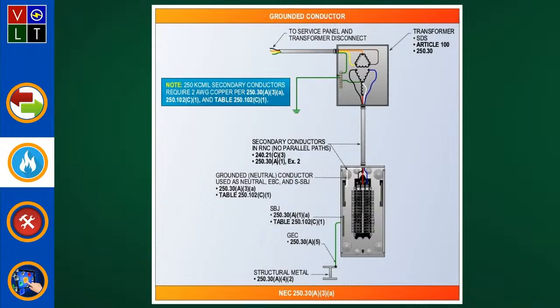Now we're going to deal with the grounded conductor. One thing I want to point out: so far we've looked at the system bonding jumper, the supply side bonding jumper, and now we're looking at the grounded conductor. You'll see the same terminology, same sizing and everything. So when I look at the grounded neutral conductor, it tells you it shall be installed with ungrounded phase conductors and shall not be permitted to be smaller than the required — listen to this — grounding electrode conductor, per what?